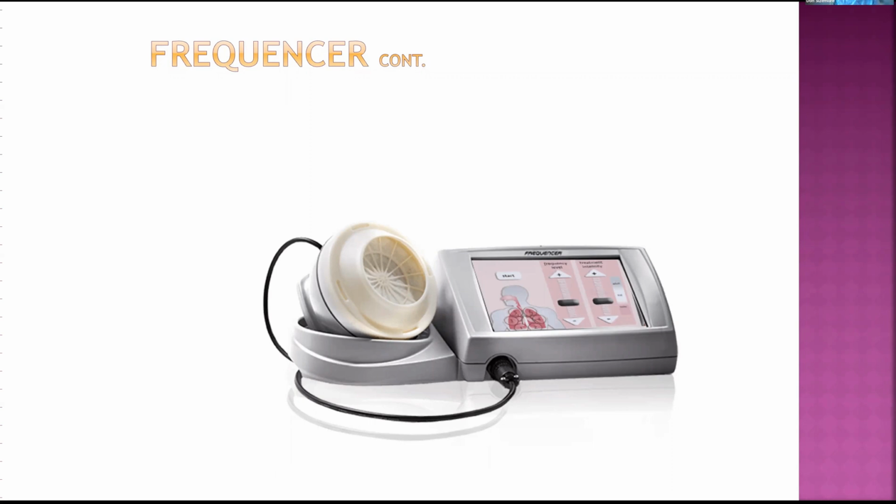You will see later in this, where we want to put the frequencer transducer on the patient. And the best scenario is to seal that circle on the patient so that the sound has nowhere to go. We know it moves like gas or like water. It's going to take the path of least resistance. So if you put the transducer on the patient and lean it up where it's not sealing on one side, you lose a significant amount of the sound out of that opening.